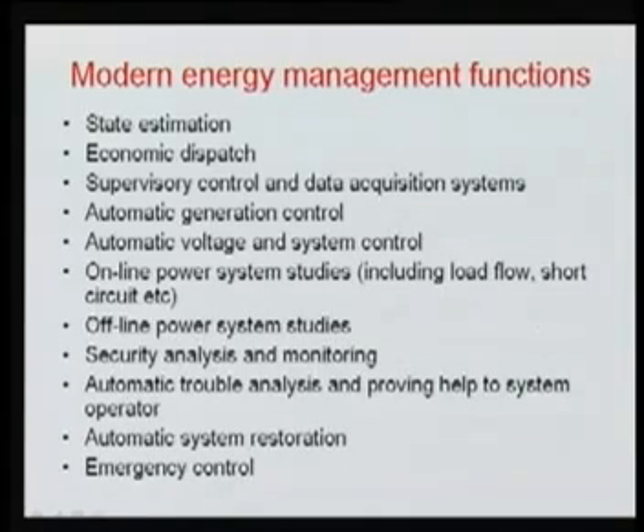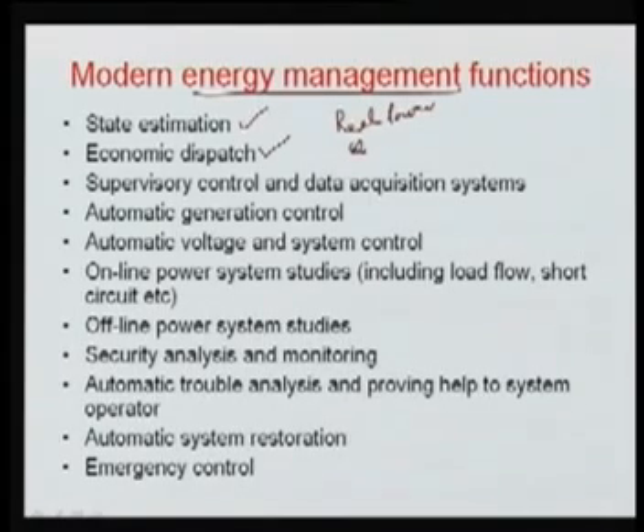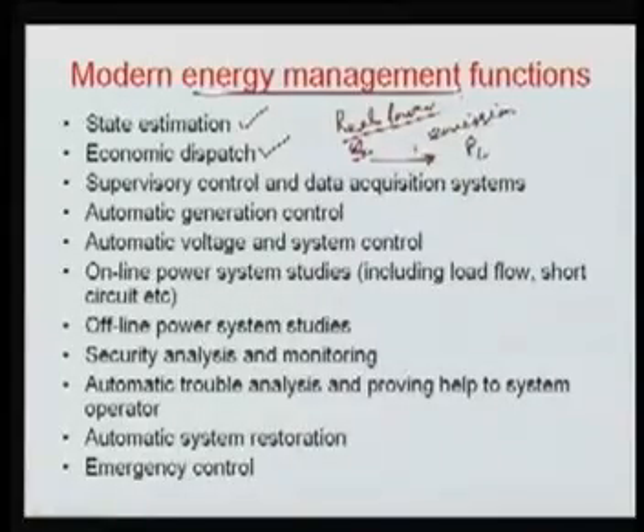Now I can summarize the various energy management functions, EMS. First, and very important, is state estimation. Then we have software related to economic dispatch. In economic dispatch, there are various types of dispatch programs: real power dispatch, reactive power dispatch, and emission dispatch. Nowadays it is also very important that we operate our power system in such a way that it emits fewer pollutants into the environment. So we can go for the minimum emission dispatch, and we can go for the reactive power dispatch, where normally we try to minimize the system real power loss. In the real power dispatch, normally called the economic dispatch, we try to minimize the total cost of all the generating units.